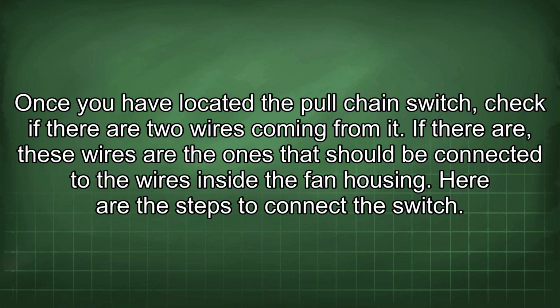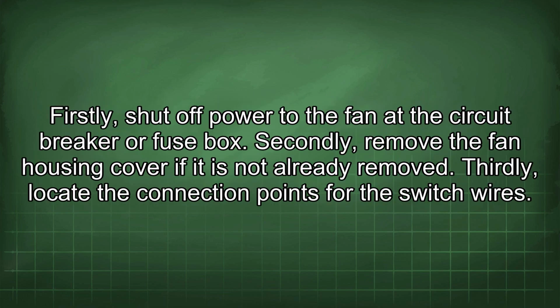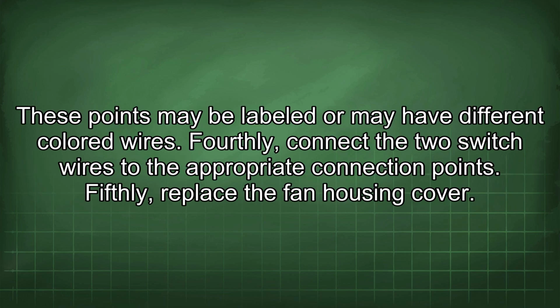Here are the steps to connect the switch. Firstly, shut off power to the fan at the circuit breaker or fuse box. Secondly, remove the fan housing cover if it is not already removed. Thirdly, locate the connection points for the switch wires. These points may be labeled or may have different colored wires. Fourthly, connect the 2 switch wires to the appropriate connection points. Fifthly, replace the fan housing cover.